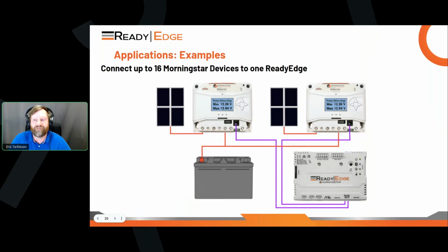The ReadyEdge sees both these devices, and all of the data available inside the ProStar MPPTs is now available in the ReadyEdge. Understanding your load status, different PV voltages, status, alarms, faults that are happening within the ProStars are both sent over to the ReadyEdge so that you don't have to log into the ProStar itself. It really simplifies the setup of these more complex small off-grid solar systems.